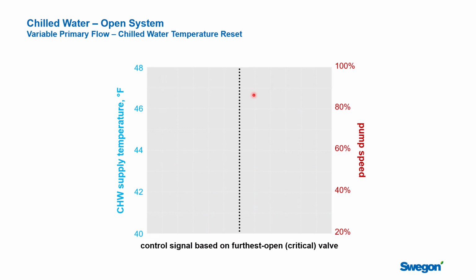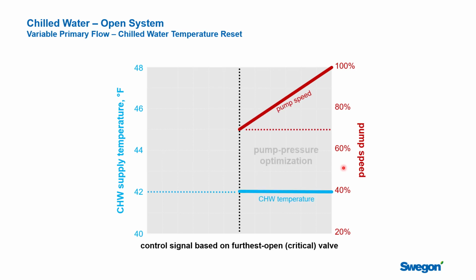So here we have a chart. You can see that this is the chilled water temperature in here, where we could be talking about a reset, and over here we've got the pump speed. What we're going to do is look at the most critical valve. It's going to be one of the primary air handling unit valves, and if you have 2 or 3 air handling units, we're going to monitor the chilled water valves at all those units and consider the one that's trying the hardest to dehumidify. At first we would maintain our 42-degree water, and we would allow the pump speed to modulate back and forth based on the load in the building.